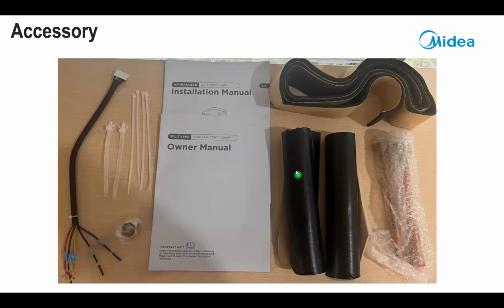These two black sleeves are for the line set connections at the AHU. It comes with adapters. If you're so inclined to use the adapters, we would prefer that you not, because that requires brazing. If you're going to use the adapters and braze, you have to flush nitrogen through the system while you're brazing. If you don't, you will end up clogging up the strainers. And of course, your installation manual and owner's manual.